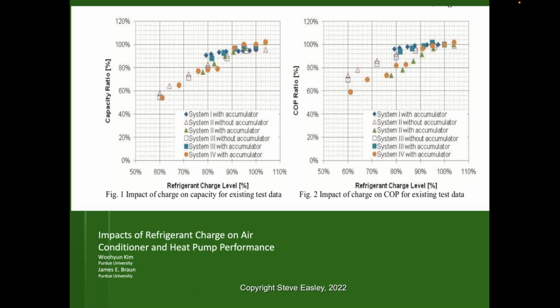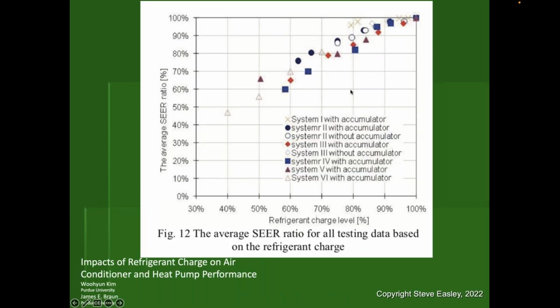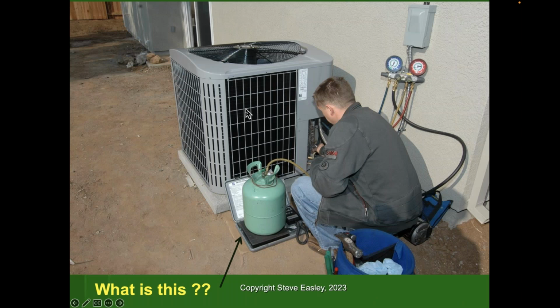Now, Purdue University did some more recent studies and found that if we look over here at 50% of refrigerant charge, and look at overall capacity, look at the curve, how much it drops off. We go from 100% to less than 60% of capacity as a result of refrigerant charge. When we look at refrigerant charge and efficiency, again, look at that. We go from 100% down to about 60% if we're undercharged. I can't emphasize the importance enough. And then the seasonal efficiency ratio drops off dramatically. So getting the appropriate charge is important.